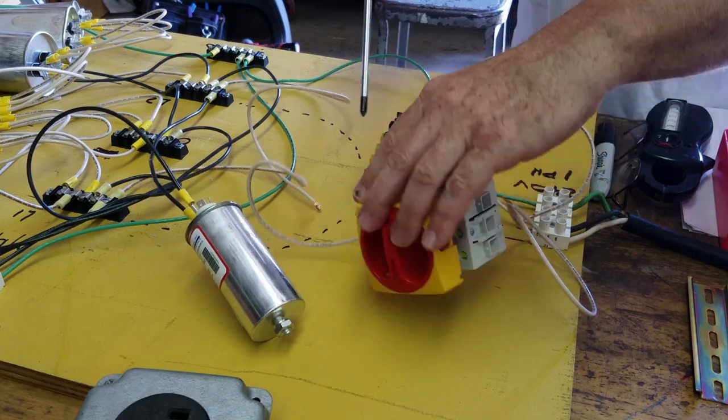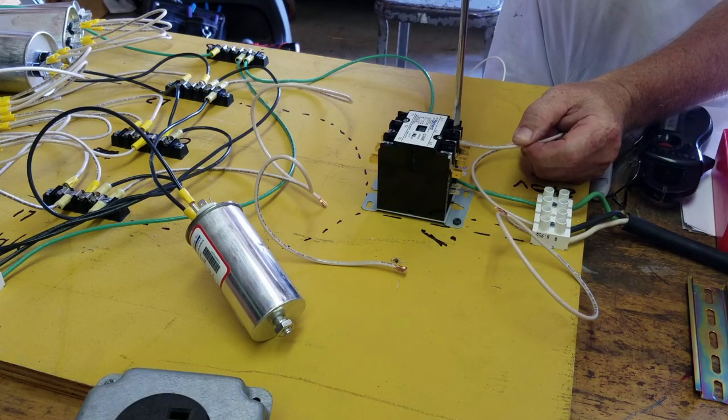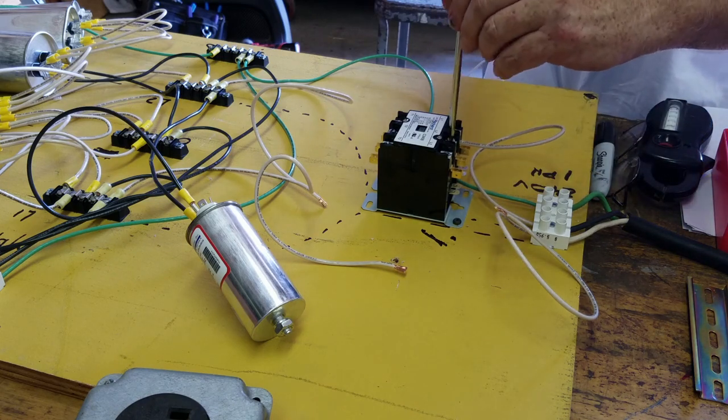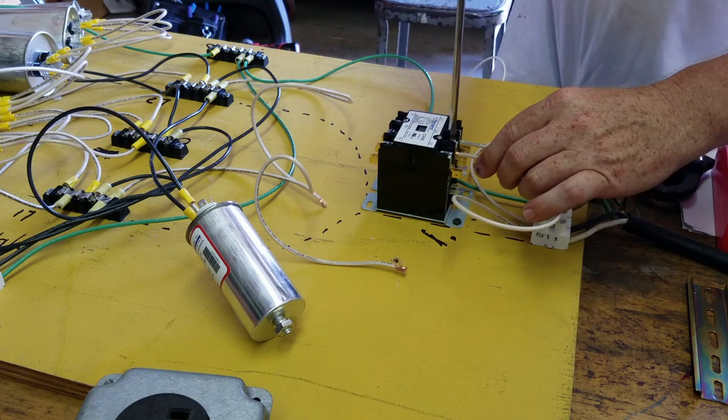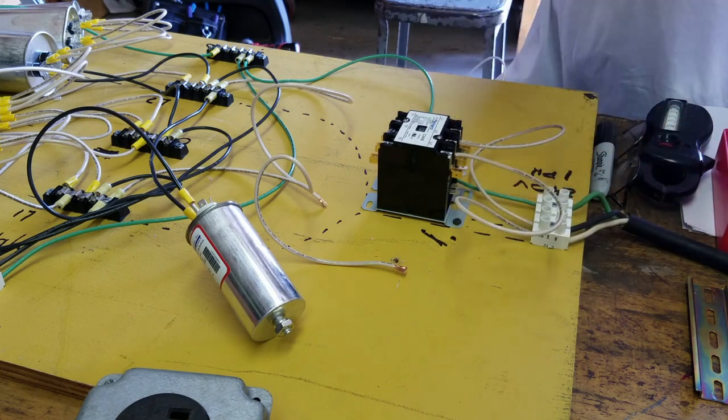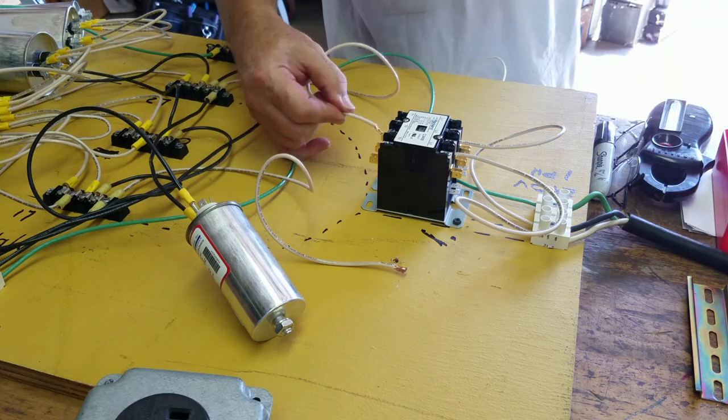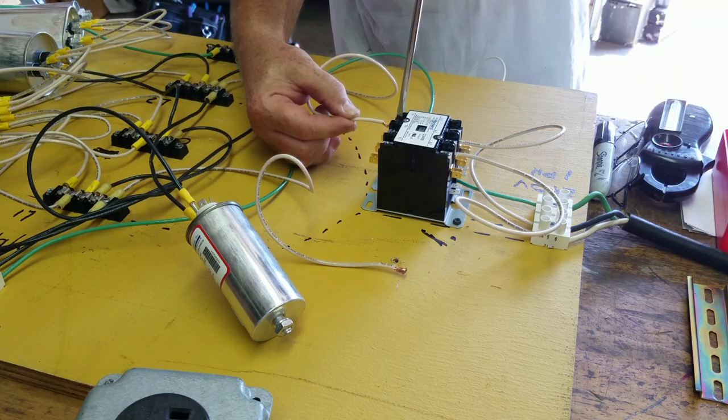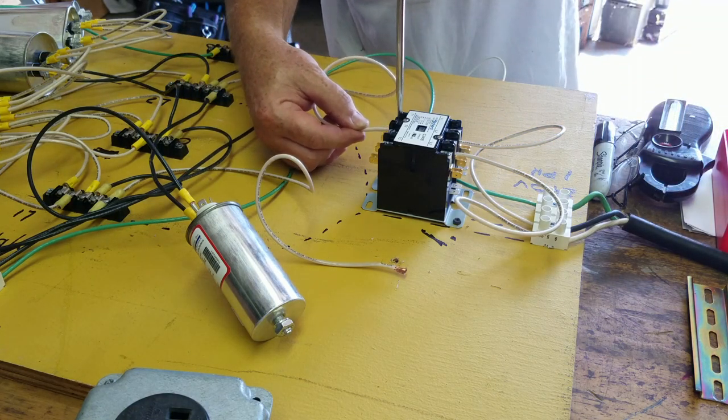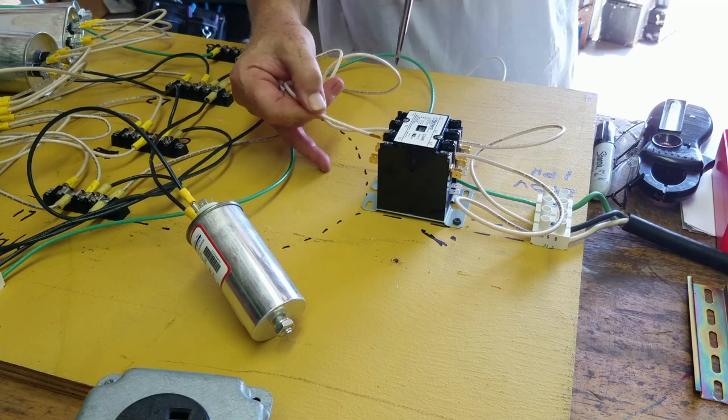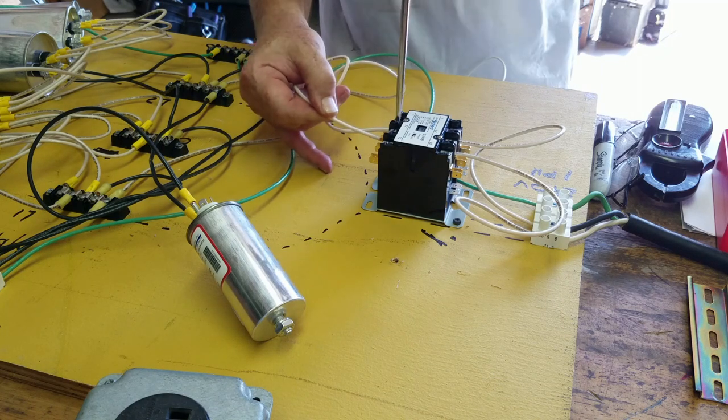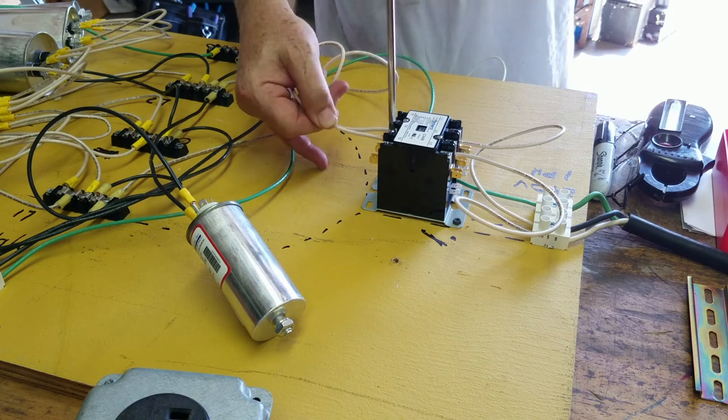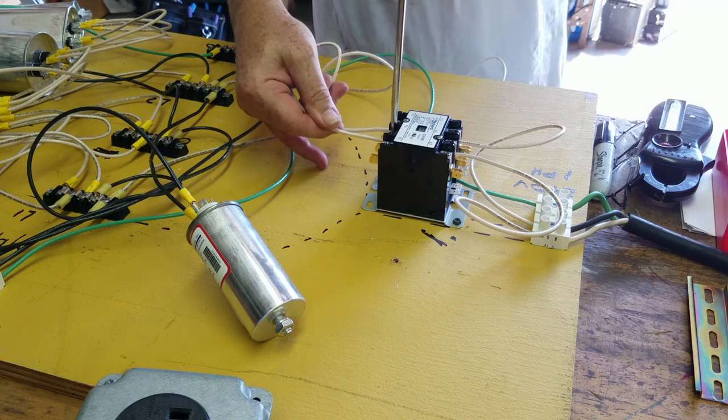Because when power is interrupted to a motor starter, when it restores, it won't reactivate. You have to physically hit the start button. Additionally, because it's a relay, the coils don't require as big a switch to activate them. I did a pretty good job of narrating what I'm doing and how this works, so I'm going to stop the voice over here and we can listen in.